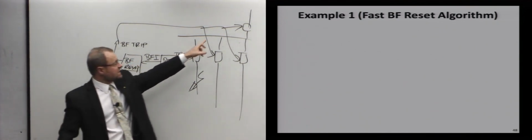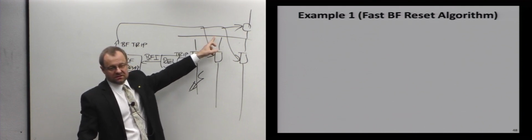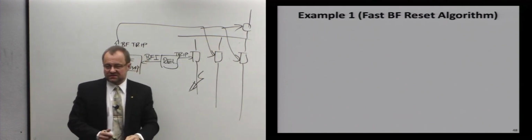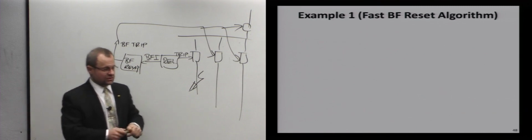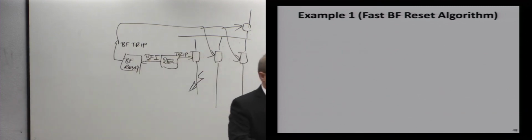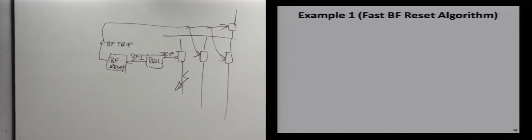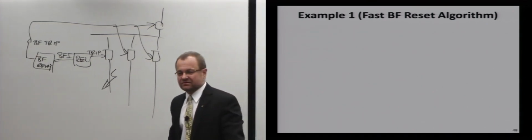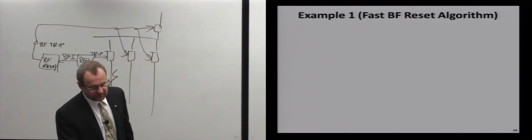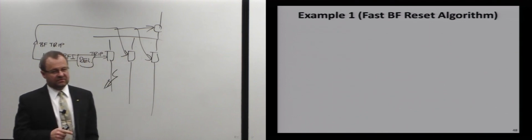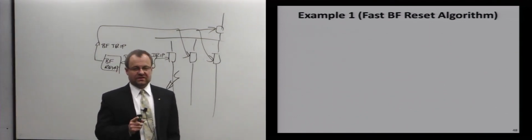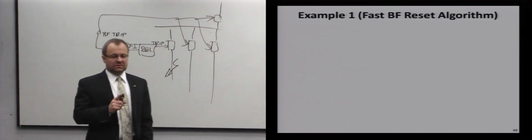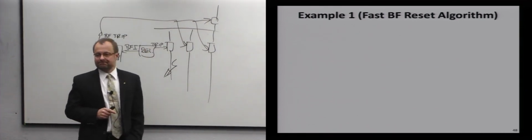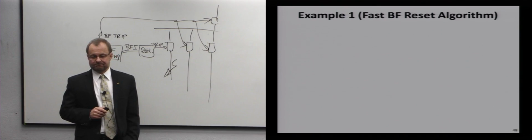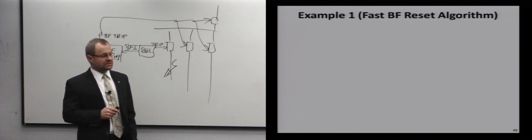We just took this entire bus. If this is a high voltage bus, a TV crew shows up and you are on the 6 o'clock news, right? And there is no reclosing on breaker fail trips. So breaker fail is a backup function. It needs to be very, very secure. So how do we detect a failed breaker? What's the principle that we typically follow?